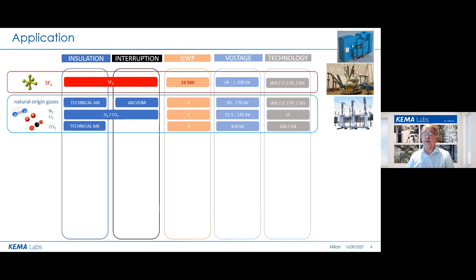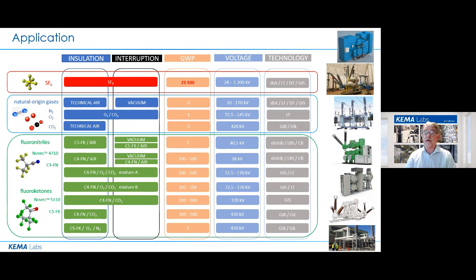Well, as you can see, new gas insulated busbar and gas insulated line developments, GIB and GIL, for 420 kV are announced and use technical air insulation. Well, then the second group of alternatives is based on synthetic F gases, the fluoronitriles and fluoroketones. The latter one, C5FK, as we call it, comes in use these days in distribution switchgear for load current interruption and insulation. High voltage insulation in 420 kV projects is still reported with C5FK mixtures. Note that C5FK mixtures have the lowest GWP of the synthetic ones. Most new synthetic gas products these days are with fluoronitriles, C4FN. As you can see, it is applied in a number of different mixtures.